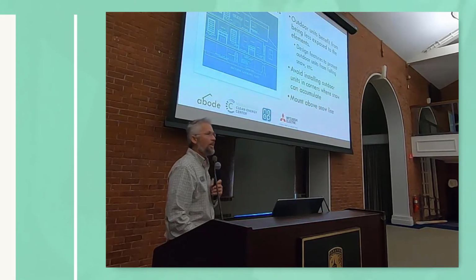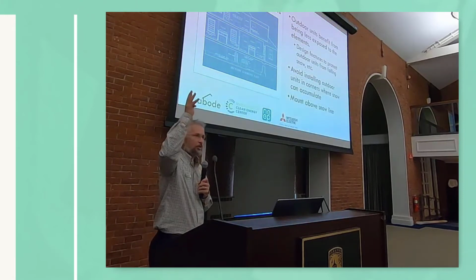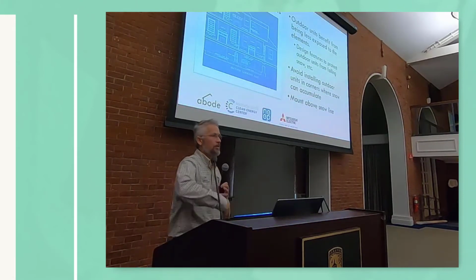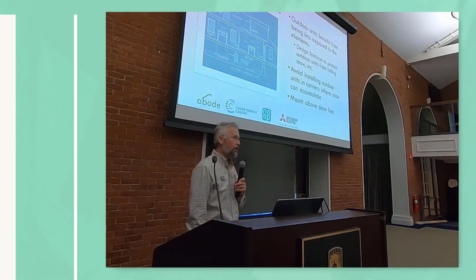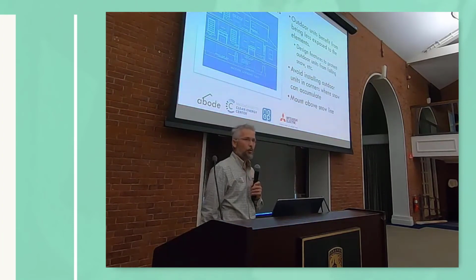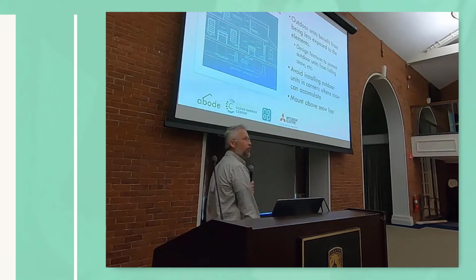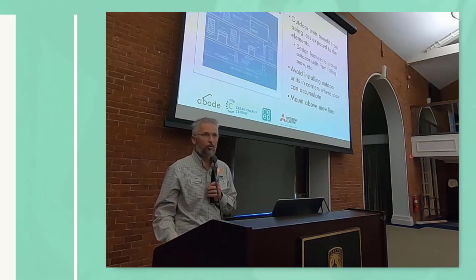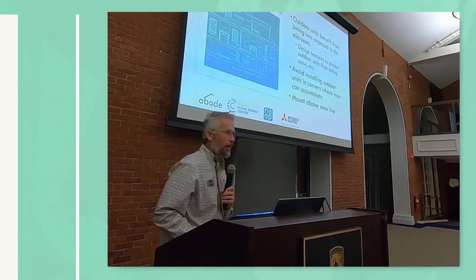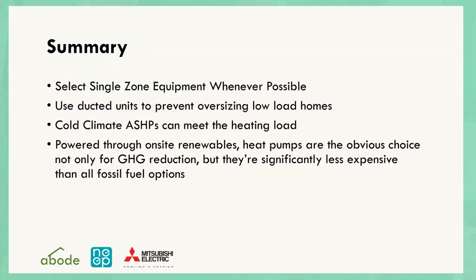Also mentioned is not being under a drip edge. If you have bulk moisture pouring onto the unit and splashing on the top of the flat roof, it goes over the top and the front and the back, and you're going to go into defrost cycle more frequently. There are caps that most distributors carry that will divert the airflow and splash it forward in front of where the air is blowing out. I'd recommend those in all circumstances where the unit has to be positioned underneath the drip edge.